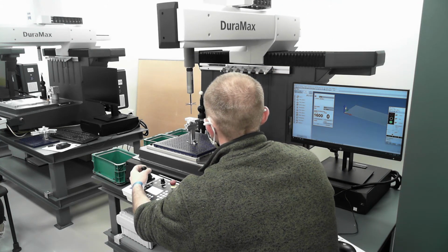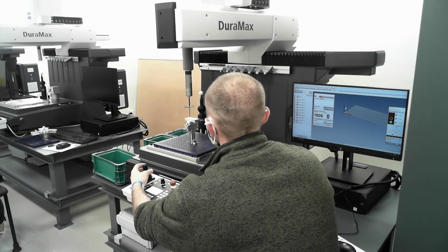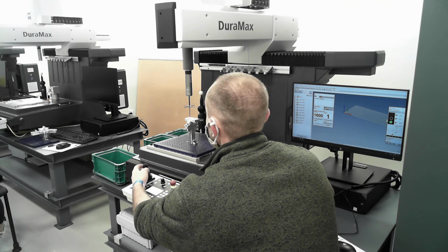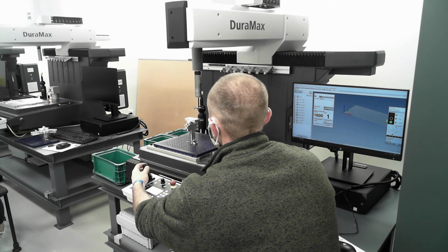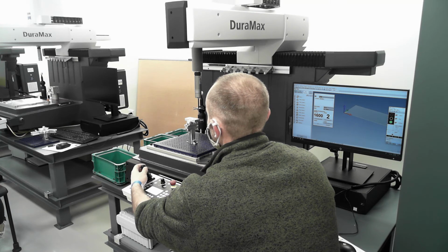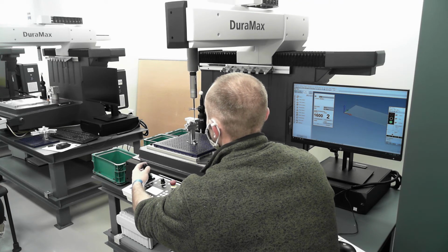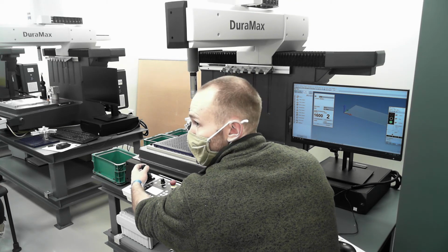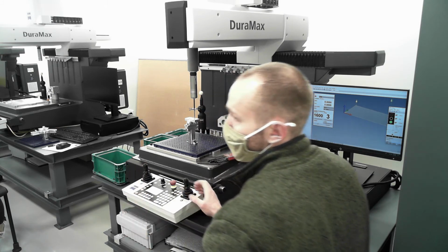I have a question. The 1,600 points that it needs to take, is that like a default or? Nope. I set that up. Oh, when you wrote the program. I set that up. That's actually for scanning. You wouldn't ever see points more than like 50 unless you're scanning. And when you're scanning, you can have an absurd number of points.